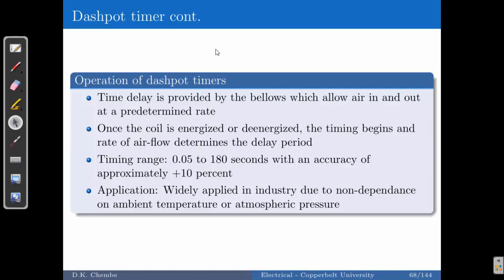Dashpot timers are widely used in industry for many reasons. One is that they are not affected by atmospheric pressure. They are not affected by ambient temperature. They are also not affected by vibration, which may occur in places like mines where open-pit blasting sends huge vibrations to the components. If the components are not durable, they may lose their operation — dashpot timers handle these conditions well.